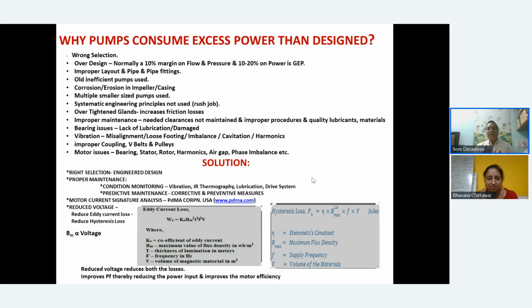They classify fault zones: if there is a power circuit issue, a harmonic issue, a stator issue, a rotor issue, an air gap eccentricity issue, or an insulation issue. So by capturing just the signature, it gives you which fault is propagating, which is more predominant and likely, and they give you a sort of expected life, so that you can take proper action. Then second is, in electrical, you can reduce voltages and run.